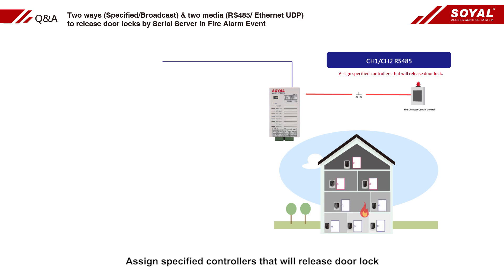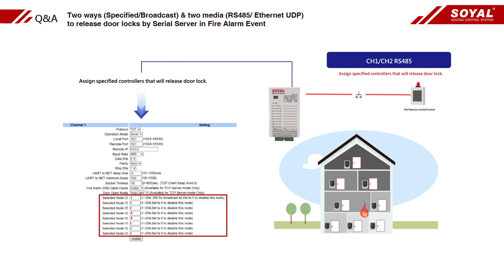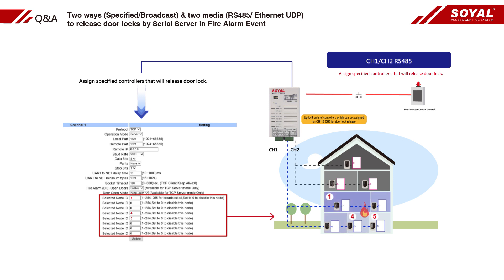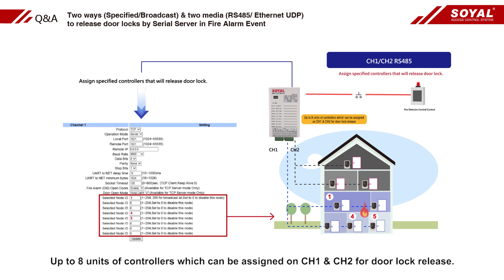Assign the specified controllers that will release door locks. Fill in the node ID of specified released controllers in the select node ID field of 727CN, channel 1 and channel 2. Up to 8 units of controllers can be assigned on channel 1 and channel 2 for door lock release.